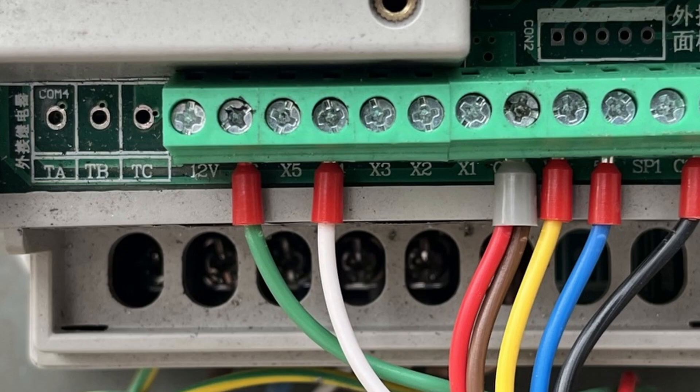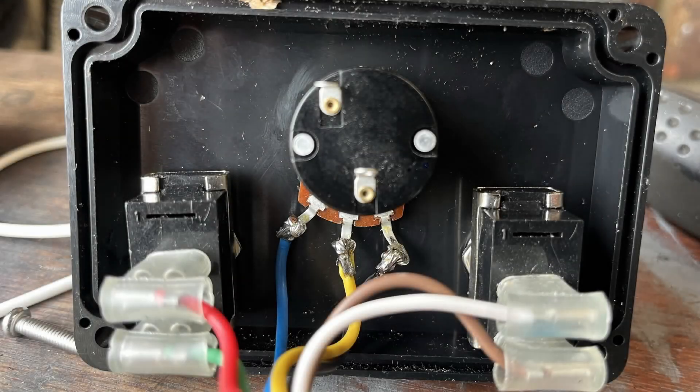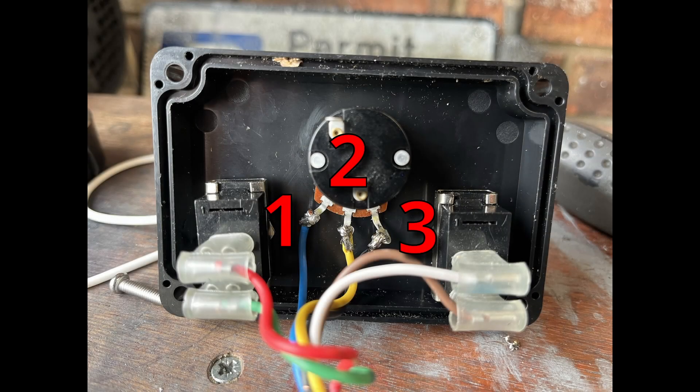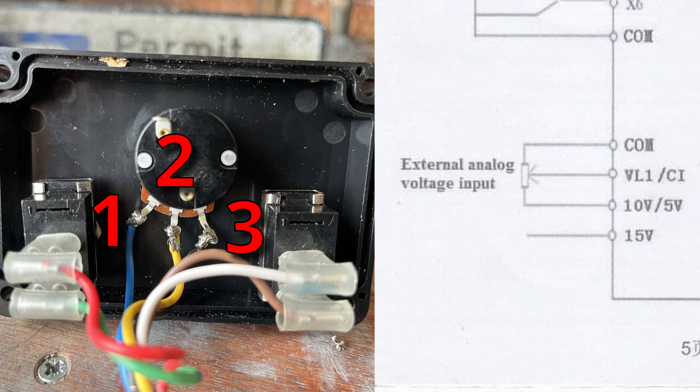My forward/reverse is already set. I'll put it to port X6 which we'll show shortly. On my panel I've got two toggle switches and a potentiometer. The toggle switches are commoned off the common. The forward/reverse goes on to X6 and the run/stop is on X4. On the potentiometer you've got three pins — one and three are fixed so it doesn't really matter which way you put those. They go on to the 10 volt or 5 volt output and common, and the center pin which is your variable frequency bit goes to VL1.